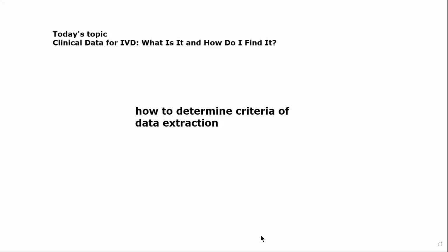We would do a competitor device search, screen, and then selection of appropriate articles that have data in them on your same safety and performance objectives, but for the competitors. So we're going to be pulling sensitivity or performance objectives or whatever they would be, and their data. So maybe, as Sarah said, the range of sensitivity might be between 90 and 100%. That's in the competitors.